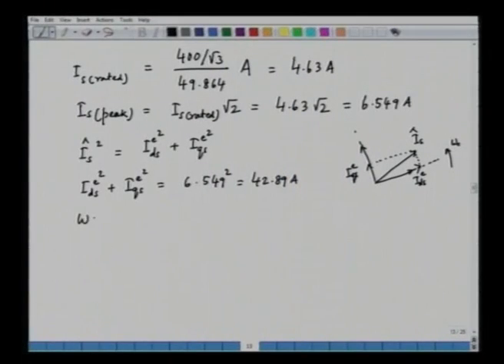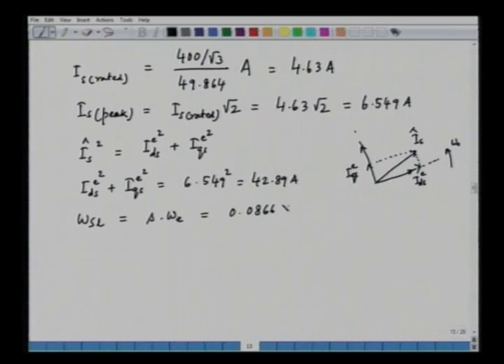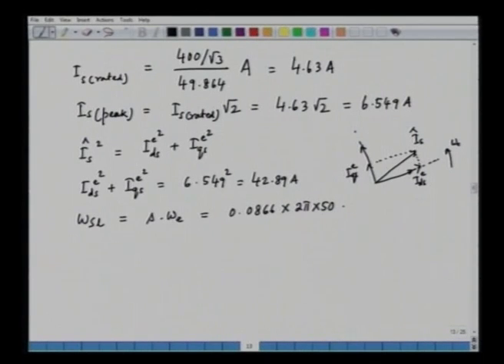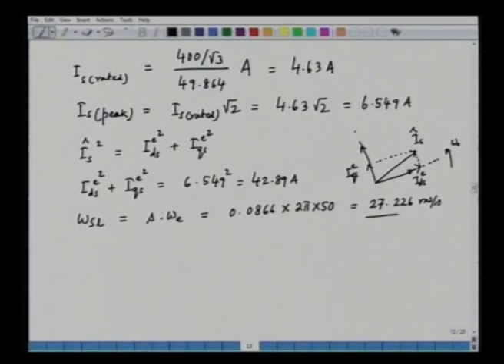Now we find the slip speed, which is an important quantity in rotor flux oriented vector control. It equals the slip multiplied by the supply frequency in radians per second. Slip speed = s × ω_e = 0.0866 × 2π × 50 ≈ 27.226 radians per second. This is one of the answers to part B.